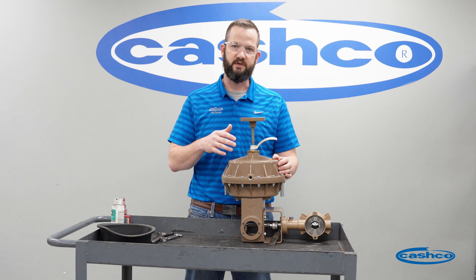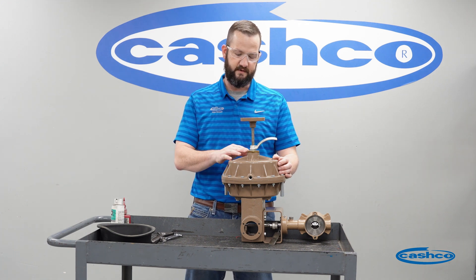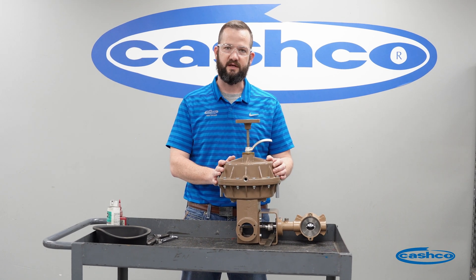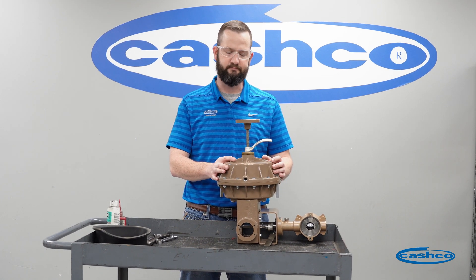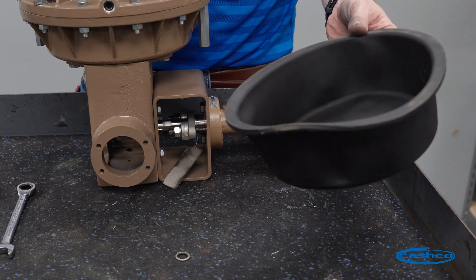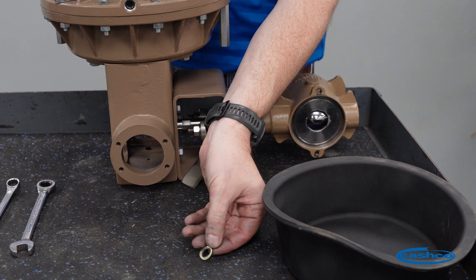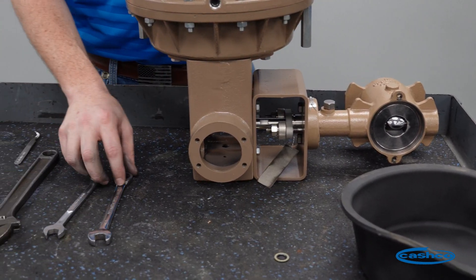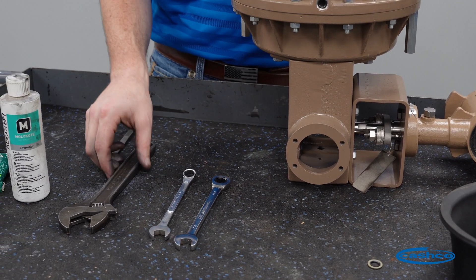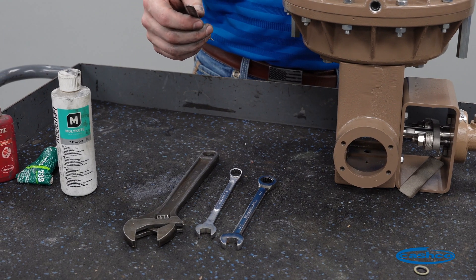It will be easiest to do this with a hand wheel assembly so that we can very easily depress the piston and lock it in place. If your Ranger actuator does not have a hand wheel assembly, contact sales at Cashco and we can definitely get you one. The items that will be needed are a new actuator diaphragm, a Stat-O-Seal washer, two open-ended wrenches depending on the size of actuator you have, a crescent wrench, and a soft smooth blunt tip tool.